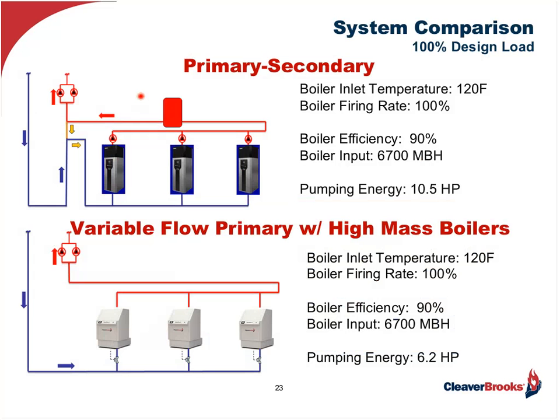Now, even here in Wisconsin, where yesterday it was 8 degrees when I got up, we don't often operate at design conditions, which is -10. Like every place else, and like I showed you on that bin chart, most of the time you're well above the minimum temperature. So even though there's no difference at full load, let's look at what happens at part load.